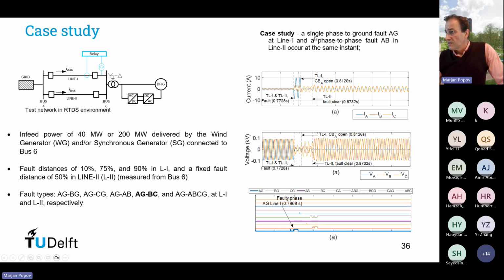This is the case, so I will just demonstrate one case here. A single phase to ground fault occurs in line one, and a phase to phase fault AB in line two occurred at the same instant. So this fault is removed by the distance protection. Here you see after two cycles the fault is removed. The other fault is removed by itself.